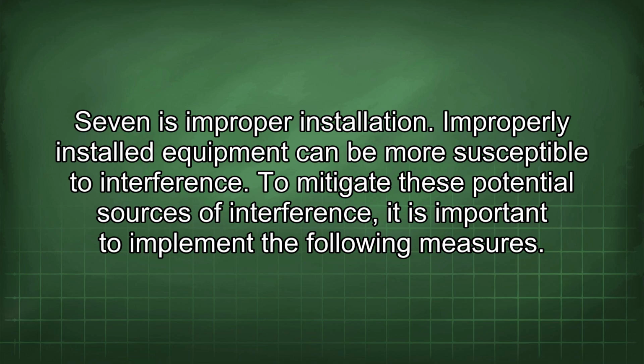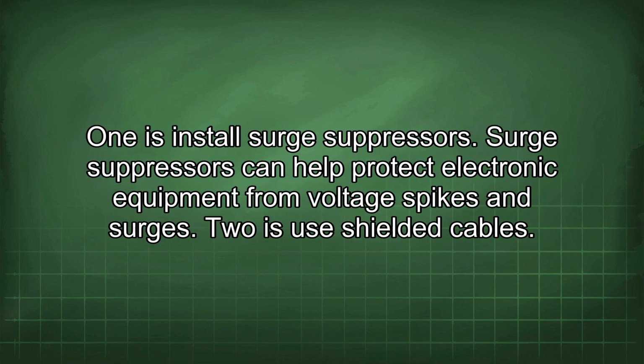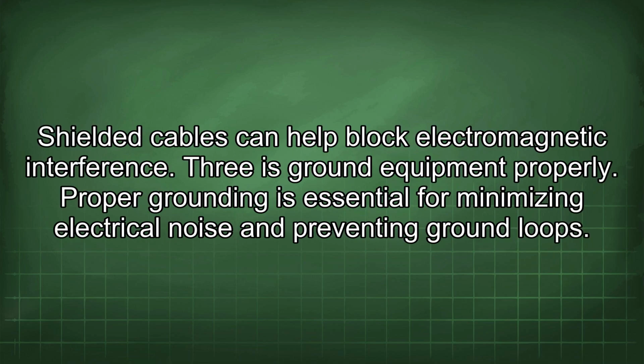To mitigate these potential sources of interference, it is important to implement the following measures. 1 is install surge suppressors. Surge suppressors can help protect electronic equipment from voltage spikes and surges. 2 is use shielded cables. Shielded cables can help block electromagnetic interference. 3 is ground equipment properly. Proper grounding is essential for minimizing electrical noise and preventing ground loops.